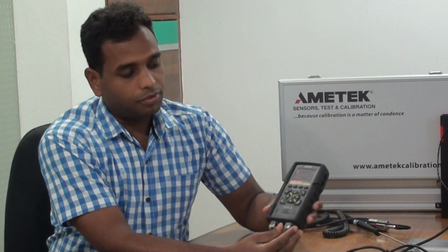It has barometric pressure, absolute pressure, differential pressure, and dual pressure inputs. So this is a complete secondary standard pressure calibrator. Here there are two pressure inputs: one designed for the lower pressure range, and one for the higher pressure range. This is for differential pressure.